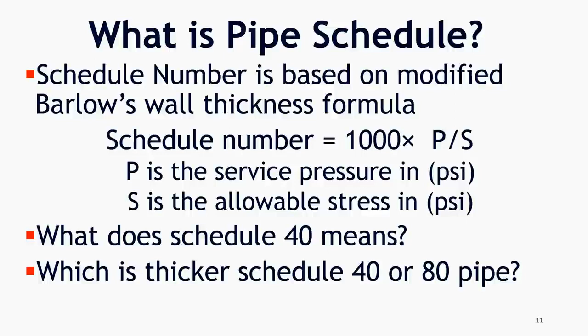So what does Schedule 40 mean? Schedule 40 is nothing but a pipe thickness designator. In simple words, you can say that for the given material, Schedule 40 pipe can withstand a certain amount of pressure. Now can you tell me which is thicker, Schedule 40 pipe or Schedule 80 pipe? Schedule 80 pipe is thicker than Schedule 40 pipe. Look at the formula of schedule number. Allowable stress for material at given temperature is fixed. That means with the increase in service pressure, schedule number will increase, which is nothing but pipe wall thickness designator.